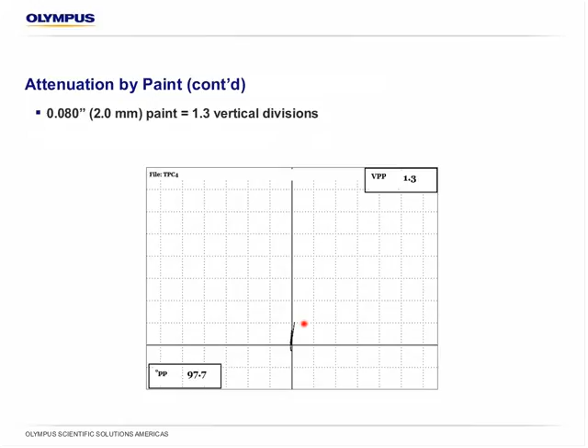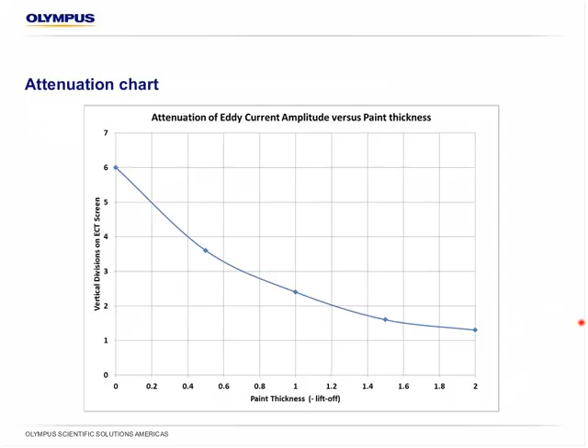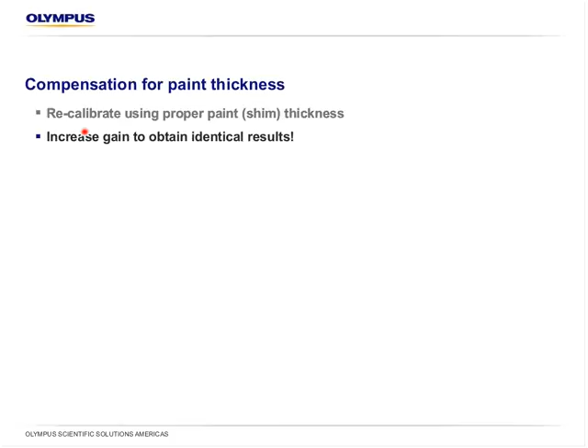So, as we plot this attenuation of the vertical amplitude in divisions against the paint thickness, we obtain an exponential decrease, which is following what the eddy current theory predicts anyway. That's not a real surprise. So what do we do? It's possible to compensate for that paint thickness in order to have a uniform sensitivity for the test, as we need to have in order to have proper detection. So it's possible to recalibrate using the proper paint or shim thickness. So we use the shims in order to recalibrate and simulate paint. So all we do is increase gain in order to obtain identical results.